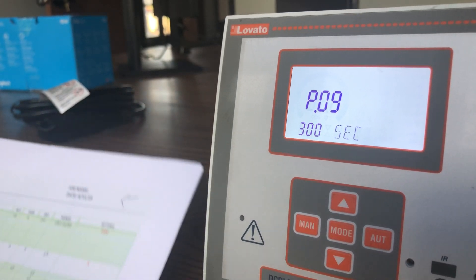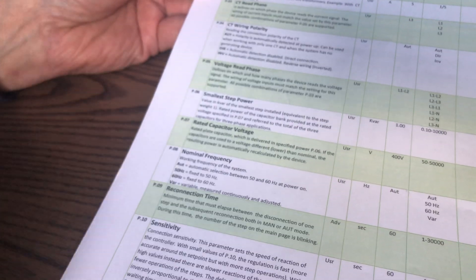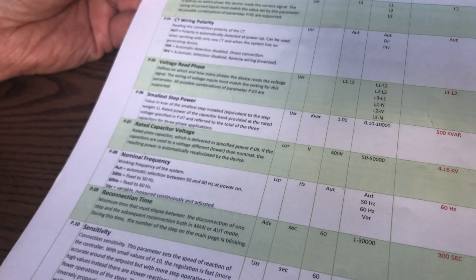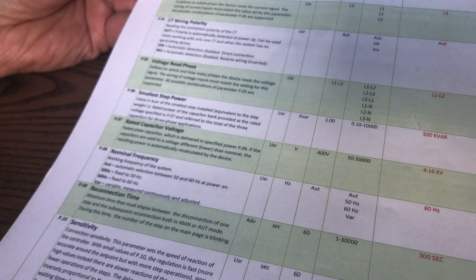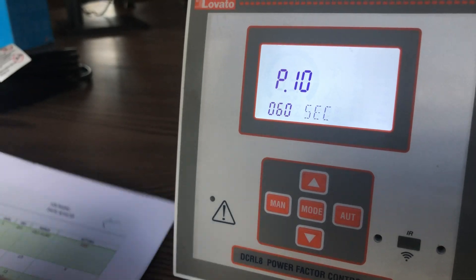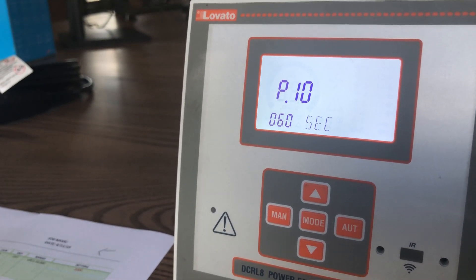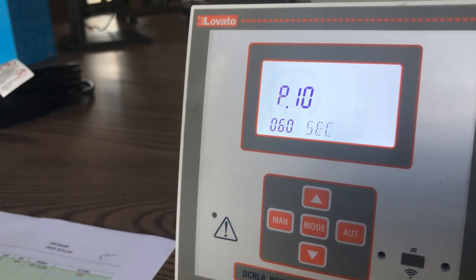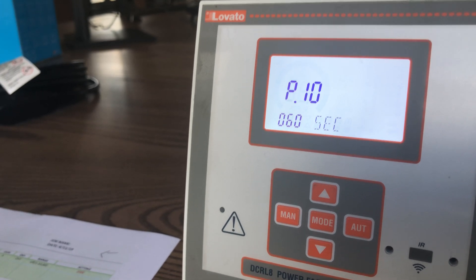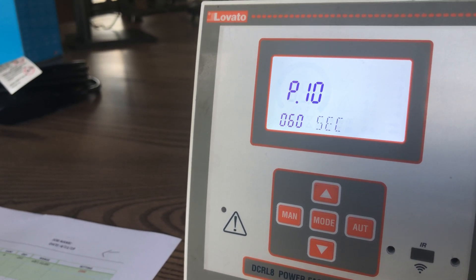P09 is your reclose timer. It says that in order to reclose a step once it opens, this meter will wait five minutes — 300 seconds — and the purpose of that is to allow capacitors to discharge between switchings. P10 is sensitivity, which is sort of like the response time between a requirement being detected and the time that it actually switches in. This is a value we've determined works best, but it is changeable.